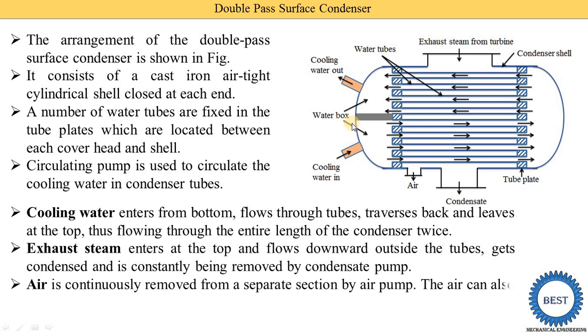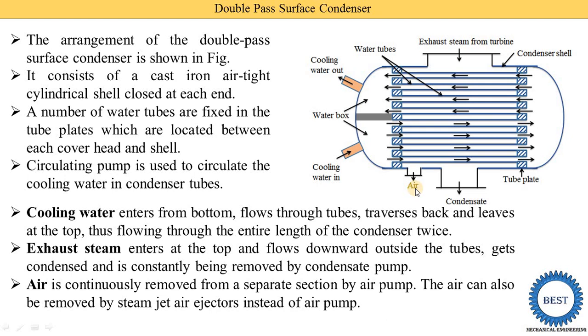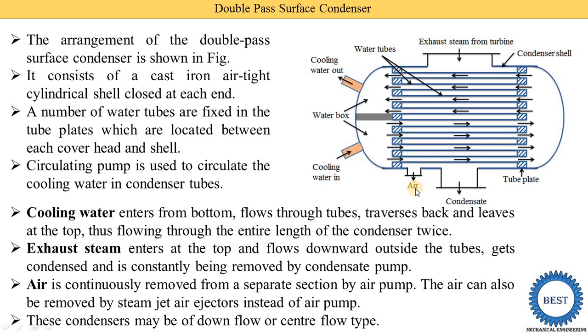Air is continuously removed by an air pump through a separate suction vent. The air can also be removed using a steam jet air ejector instead of the air pump. This condenser may be of down flow or center flow type. In down flow type, the air vent is provided at the bottom of the condenser. In center flow type, the air vent is provided at the center of the condenser, so air is removed from the center.